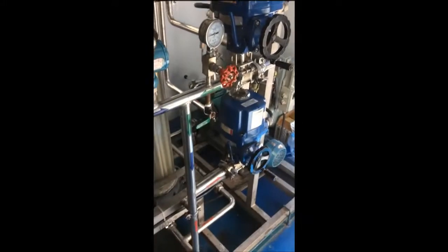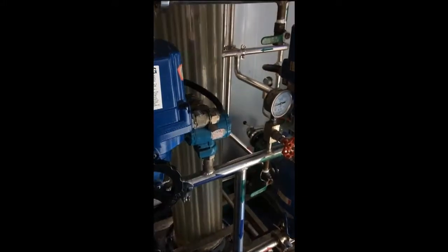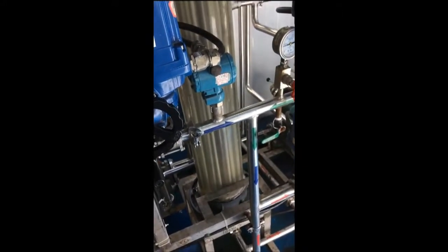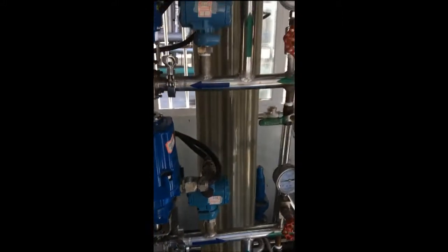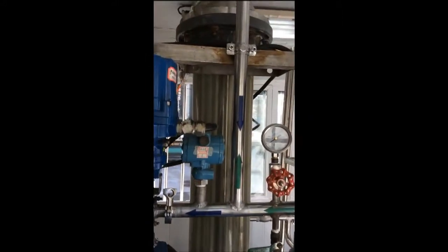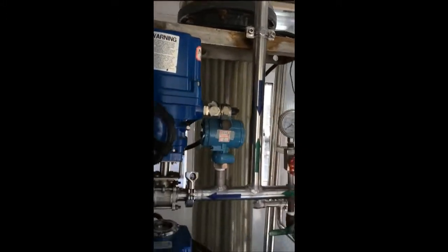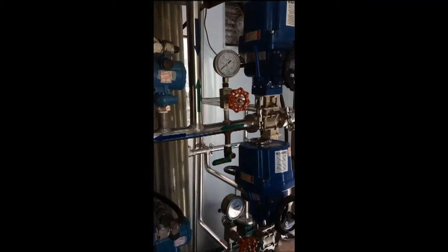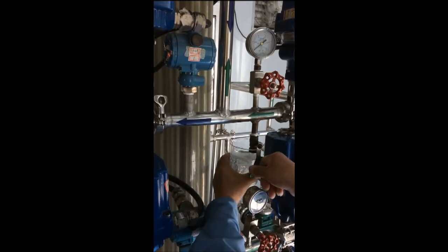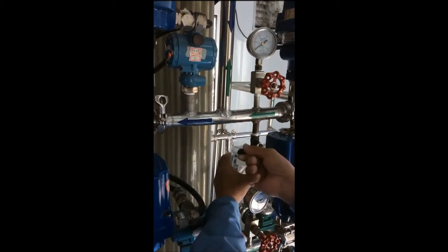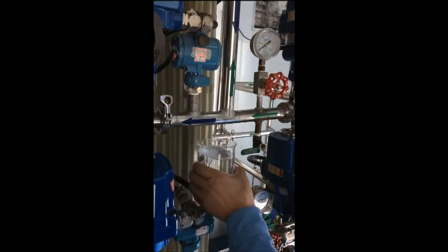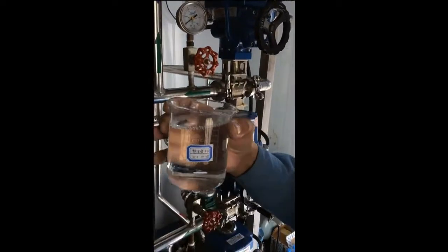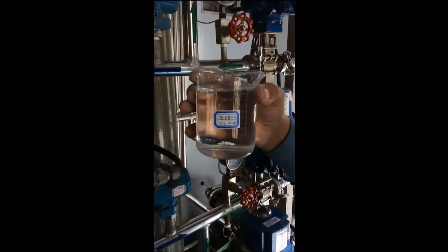These membranes do not have a skin layer on them, and we put a skin layer on them by adding a powder before the filtration run, a very thin layer, and then that layer acts as the skin layer. It allows us to increase our flux rates dramatically on the membranes, 10 to 15 times. It also lets us operate at very, very low pressure, below 1 bar. In fact, we won't go any higher than 1 bar.